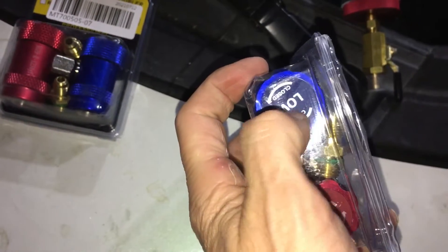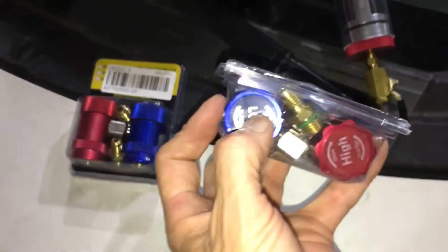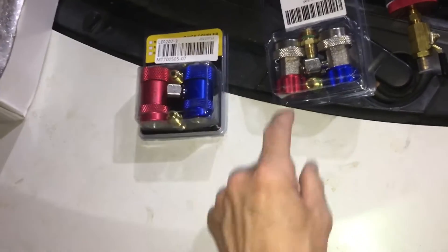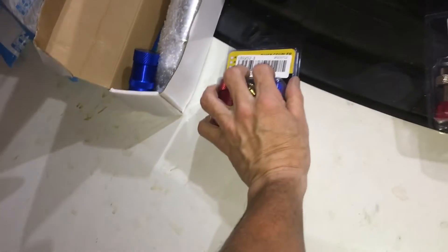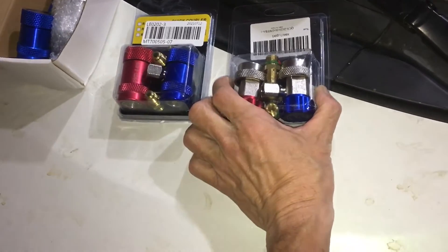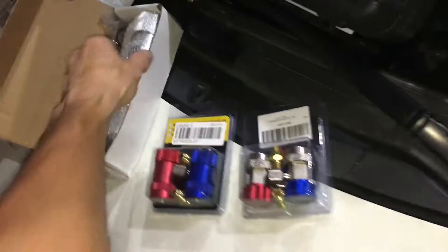But if you've seen my videos on how these things leak — they leak underneath the sticker, right where the little rivet or stud holds your cap on. Put some silicone grease or Nylog right there and stick your sticker back on, because when they leak, they leak right there. Yellow Jacket leaked right there, MasterCool leaked right there, same as the cheap Chinese ones. Whether I paid $50-80 for Yellow Jackets or $14 for a cheap eBay one, they both eventually leaked — fixed the same way with Nylog on the threads and that rivet.